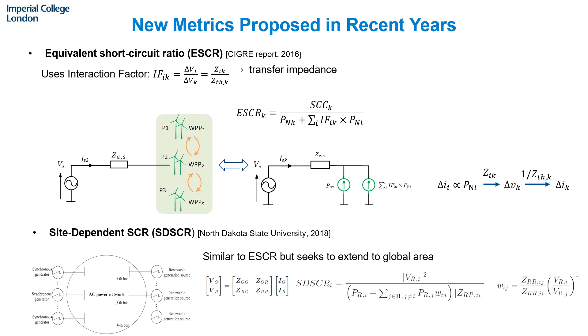Previous methods treated all sources as voltage sources, but current sources were not actually included. We know we have grid-following inverters, and they should be treated as current sources when calculating the short circuit ratio. To solve that, our idea is to change the nodal admittance matrix of the system into a hybrid matrix by picking out the current source in the system and swapping their input and output.